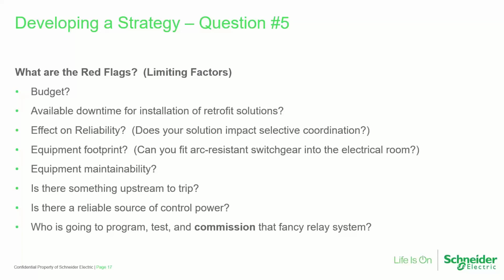Do they have any effect on reliability? Selective coordination, for example. What about equipment footprint? That can be an issue if you're looking at arc resistant gear. How do you vent the fumes or whatever? Equipment maintainability. Is there something upstream to trip? If we put in an optical relaying system to protect the main breaker section in a low voltage switchboard, well, you can't protect that low voltage main section by tripping the main of that switchboard. We need to trip something farther upstream. We've seen systems specified where there was nothing upstream to trip, so it really defeats the purpose of spending the money to put that in.